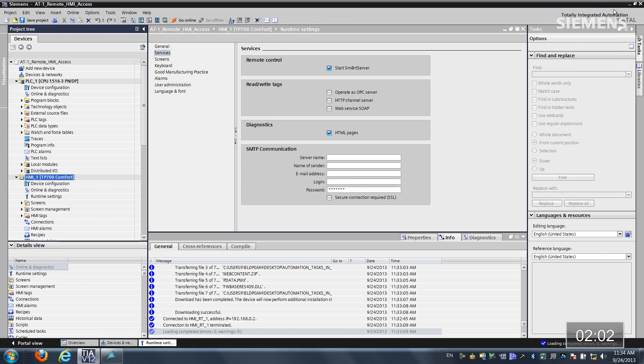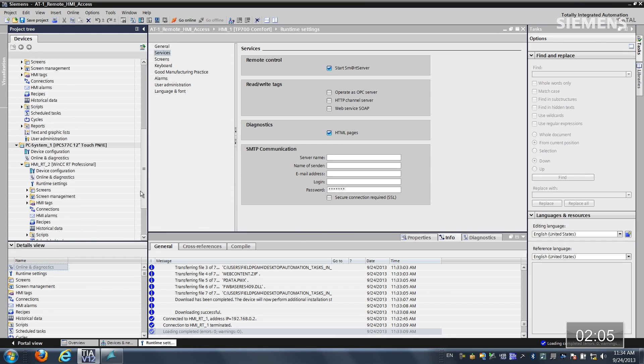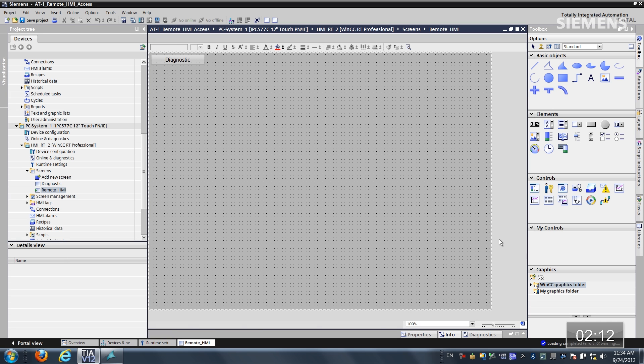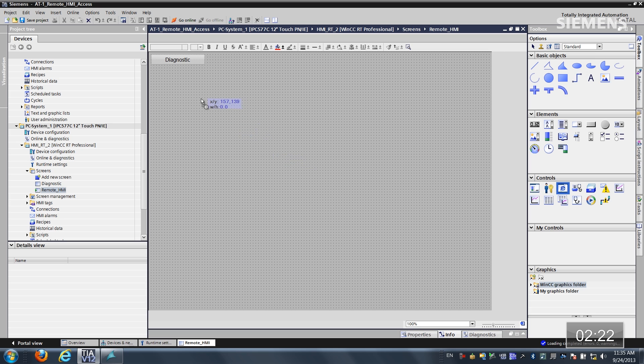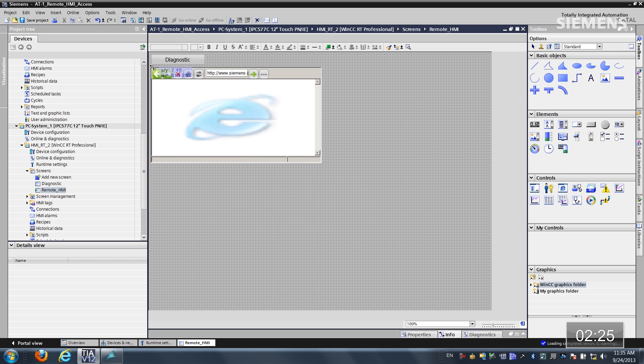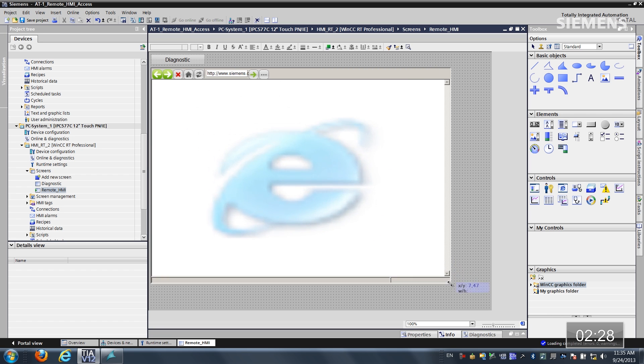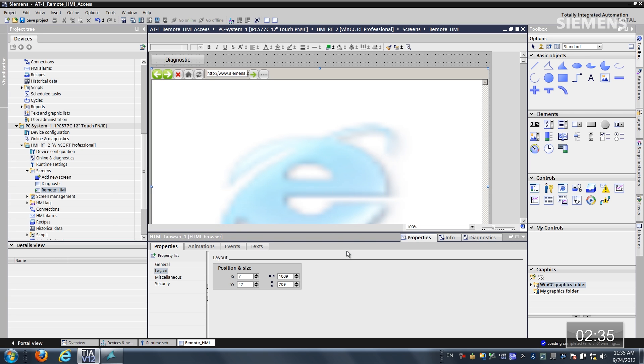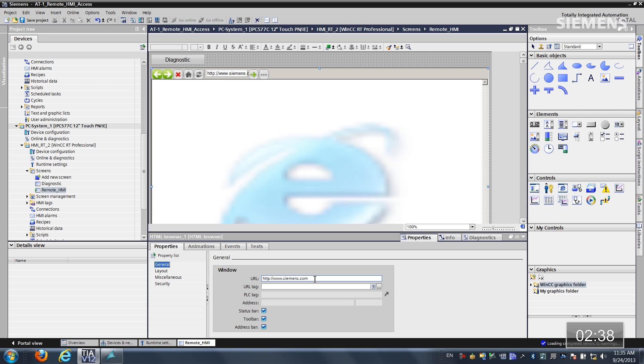So how about integrating this into our SCADA system? I'll close this out and go down to the actual screens of this PC Professional Runtime, then go to Remote HMI. There's nothing here other than a diagnostic button. If I come over to my controls, I have this ActiveX Control HTML browser — I'll drag and drop it in, then resize and refit it. To tie this to the actual HMI panel, I'll give focus to it, right-click, go to Properties, then General. At the URL field, I'll type in the IP address: 192.168.0.2, and click Enter.